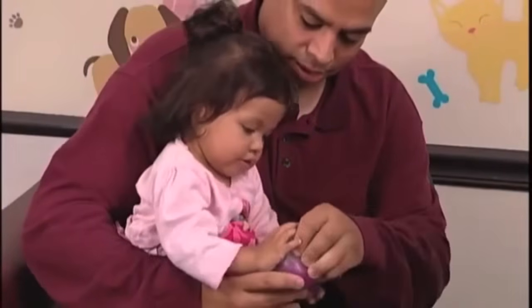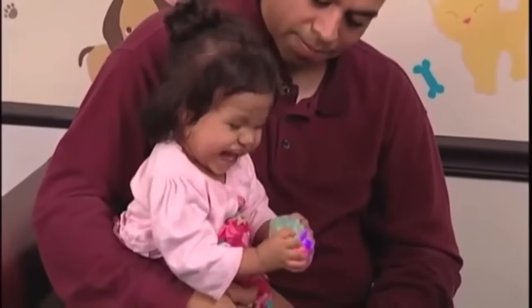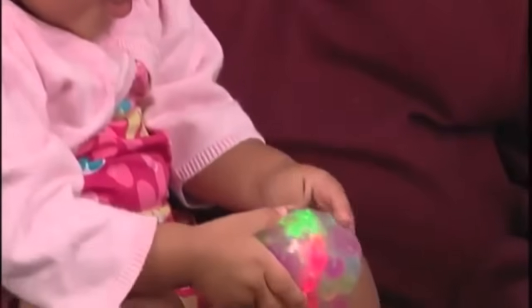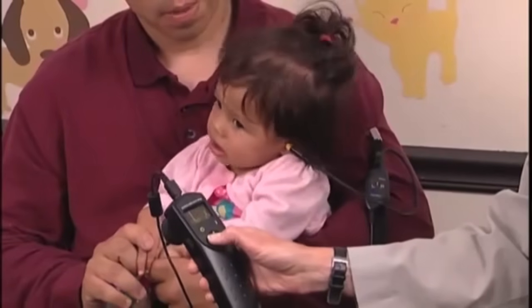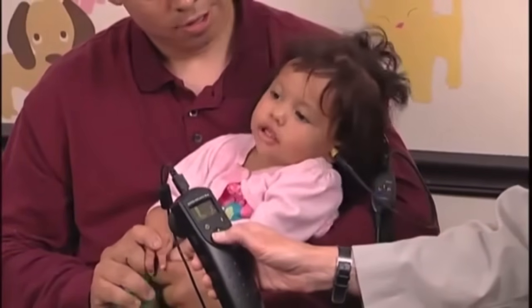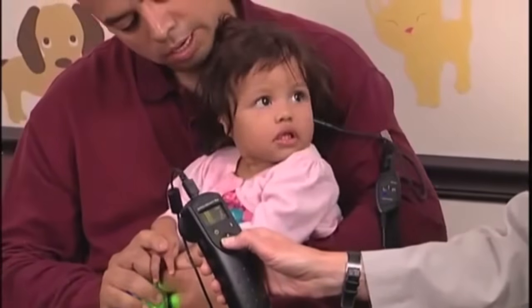When testing young children, quiet toys should be used to distract the child during the testing process. Ideally, these toys should be something the child can hold on to. This keeps their hands occupied, which prevents them from pulling the probe out of their ear canal. Here again, attach the probe enclosure close to the patient's neck. This way, you can keep any weight off the probe cable and away from the child's grasp. In some cases, you may find it preferable to attach the probe enclosure to the caregiver rather than the child. For these younger children, some users prefer to allow the child to adjust to the probe in their ear before beginning a test, while other users prefer to begin the test prior to inserting the probe into the ear canal. The latter technique allows you to have both hands free to place the probe and divert the child's attention. This is really a matter of user preference, since the test will not begin until a proper seal with the ear canal has been made.